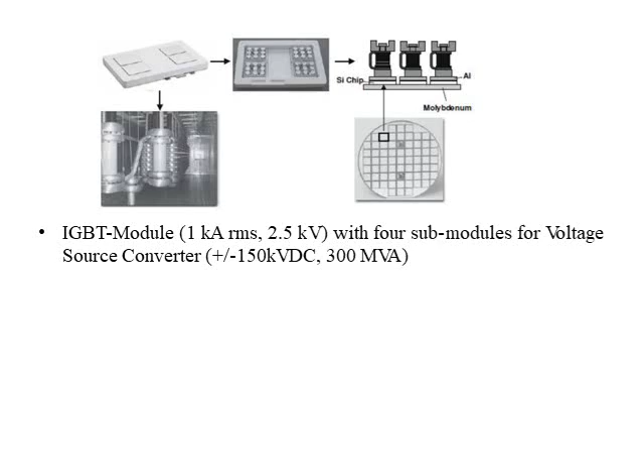The next figure shows an IGBT module of 1 kiloampere RMS, 2.5 kilovolt with 4 sub-modules for a voltage source converter, that is plus minus 150 kilovolt DC and 300 MVA. Each sub-module contains 9 chips, of which 6 are IGBT chips and 3 are diode chips.